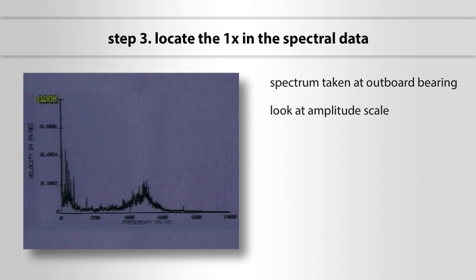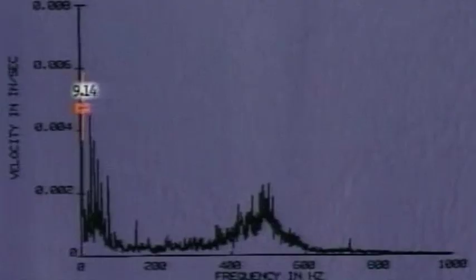It only reaches to .008 inches per second of velocity. These are very, very small vibrations we're seeing. The graph has been scaled to make the peaks more visible. By moving the cursor around, we find a peak at 9.14 Hz, and we have an exact match for the calculated one-times.